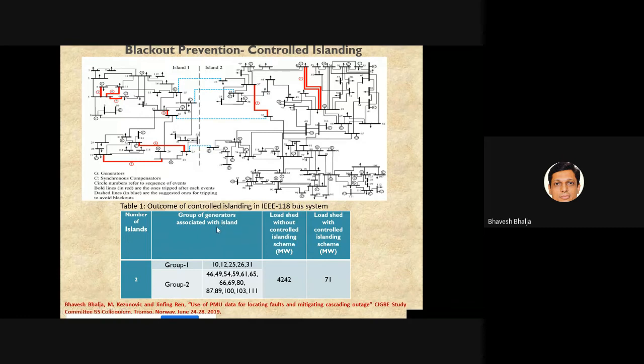And then we have the group of generators associated with the island, when islanding is carried out, which number of generators are associated with that. And load shed without control islanding means, if I do not adopt this blackout prevention algorithm, then you have to remove this much load, in megawatts.